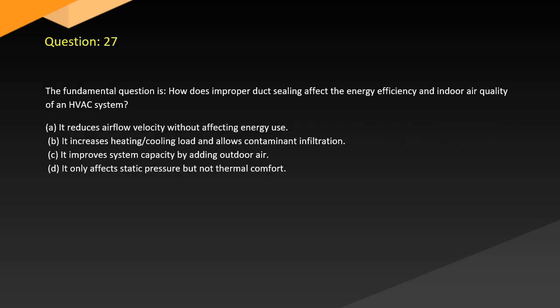Question 27. The fundamental question is, how does improper duct sealing affect the energy efficiency and indoor air quality of an HVAC system? A. It reduces airflow velocity without affecting energy use. B. It increases heating and cooling load and allows contaminant infiltration. C. It improves system capacity by adding outdoor air. D. It only affects static pressure but not thermal comfort.